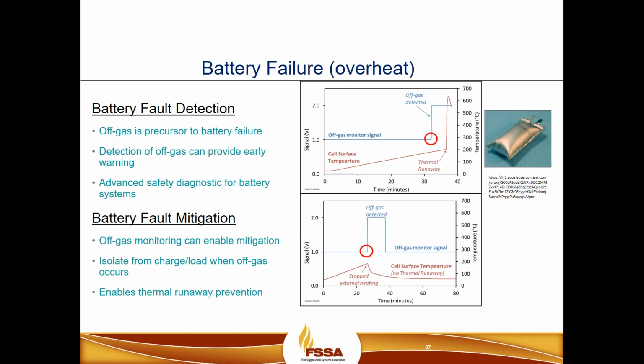The first graph at the top here is representative of the previous slide, where it shows how the cell is heated at 5 degrees Celsius, and it reaches thermal runaway here at roughly, again, 37 minutes. And the golden time factor in between is where the off-gas monitor detected the event. So for this particular test, the golden time was roughly about 6 minutes.